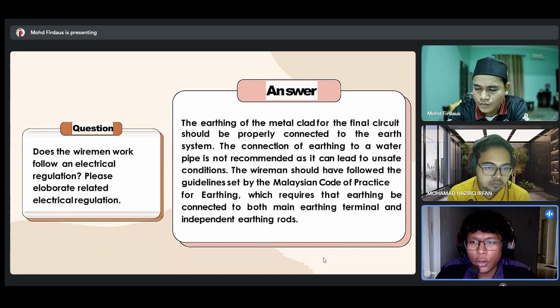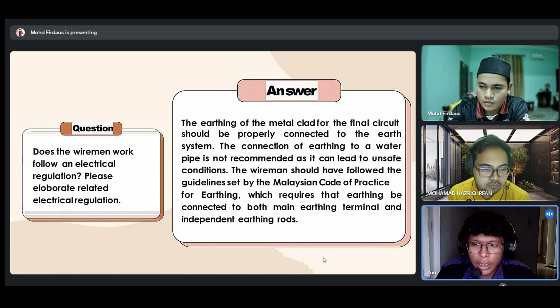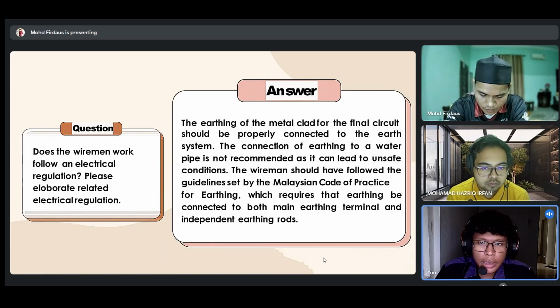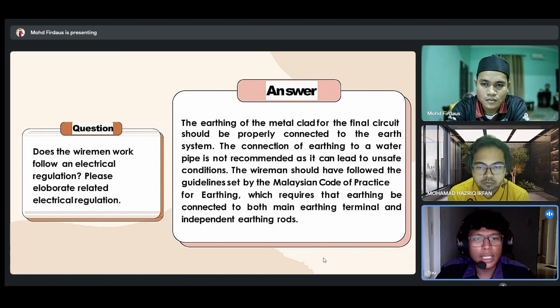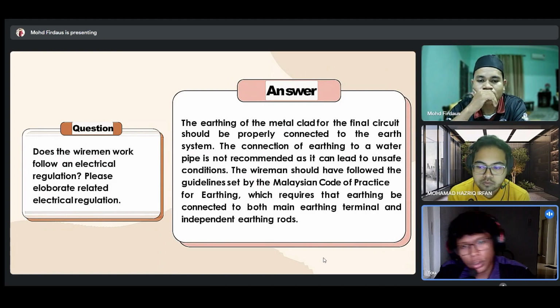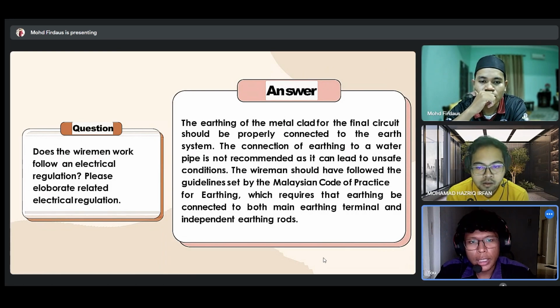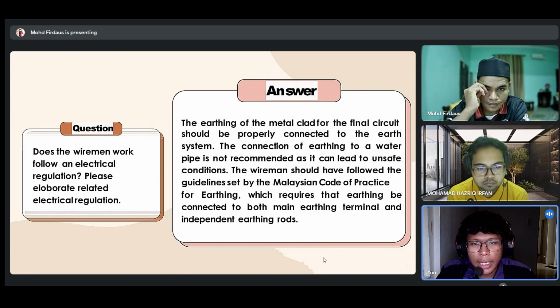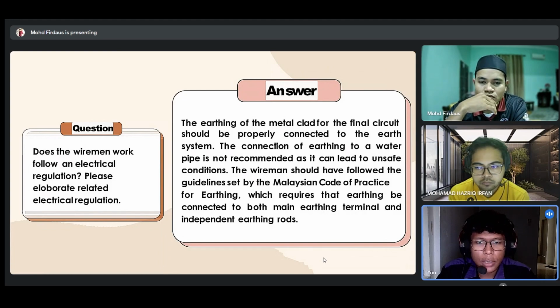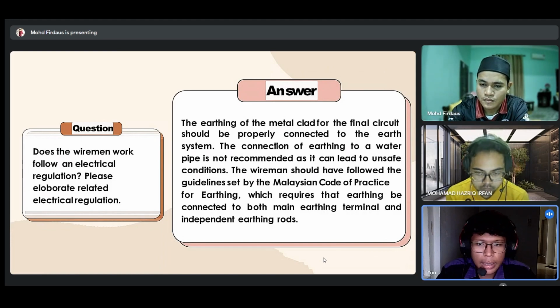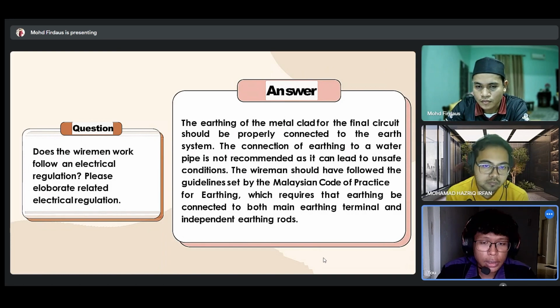Does the wireman's work follow electrical regulation? Please elaborate on the related regulation. The answer is: the earthing of the metal clad for the final circuit should be properly connected to the earth system. It should not be connected to the water pipe, but to the earth system instead. Connecting the earthing to a water pipe is not recommended as it can lead to unsafe conditions, as mentioned before. The wireman should have followed the guidelines set by the Malaysian Code of Practice for Earthing, which requires that earthing be connected to both the main earthing terminal and independent earthing rods.